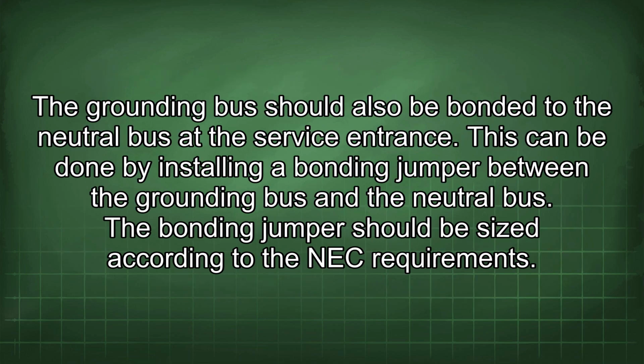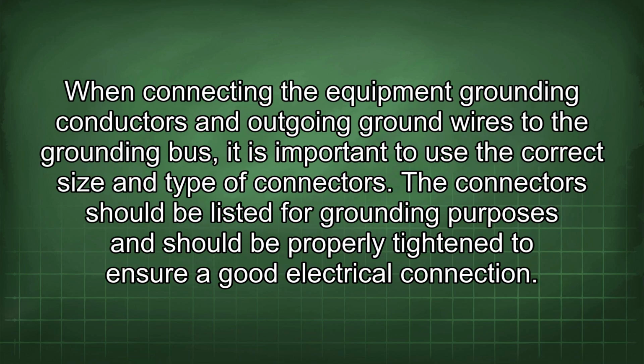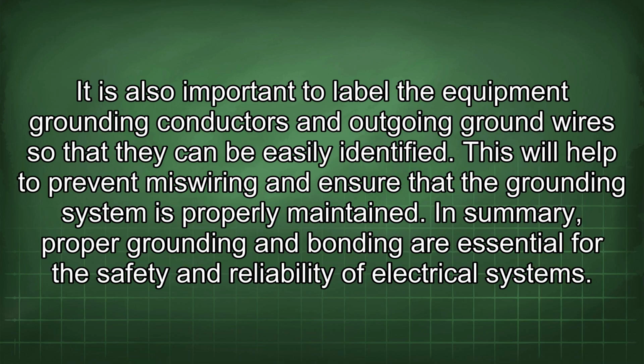The grounding bus should also be bonded to the neutral bus at the service entrance. This can be done by installing a bonding jumper between the grounding bus and the neutral bus. The bonding jumper should be sized according to the NEC requirements. When connecting the equipment grounding conductors and outgoing ground wires to the grounding bus, it is important to use the correct size and type of connectors. The connectors should be listed for grounding purposes and should be properly tightened to ensure a good electrical connection. It is also important to label the equipment grounding conductors and outgoing ground wires so that they can be easily identified. This will help to prevent miswiring and ensure that the grounding system is properly maintained.